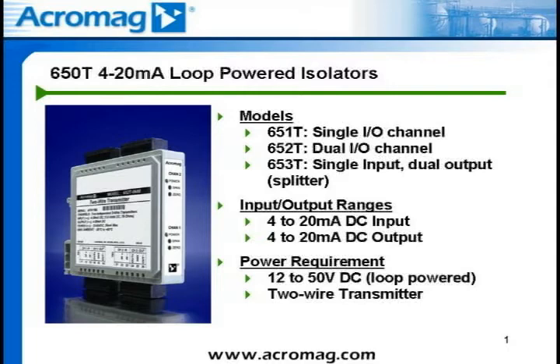Process current outputs are also 4 to 20 milliamps DC analog signals and are current limited to 36 milliamps DC. Since these are two-wire transmitters, 12 to 50 volts DC is required to drive the output loop. The supply voltage must be chosen to supply full-scale current to the load, 12 volts to the isolator, and any voltage line drop.